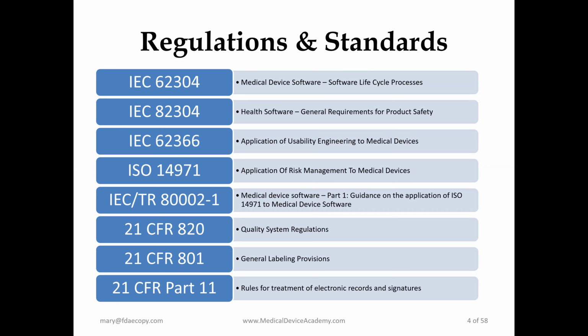One comment here, 14971, the committee that's revising 14971 just finished their job. So they have their final version, and they expect it to be released in December for purchase. So anybody that's got 14971 2012 or 2007, those versions are going to become obsolete by December. And the draft version was released last year. So if you're interested, we actually have a blog about it on our website. But you're definitely going to have to purchase a new version of your 14971 standard this December.